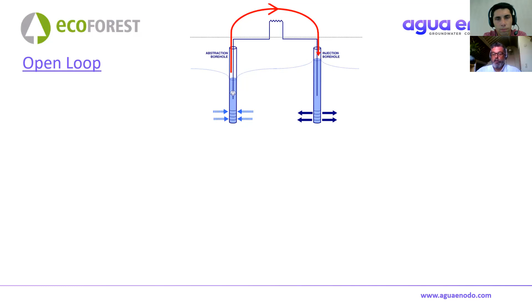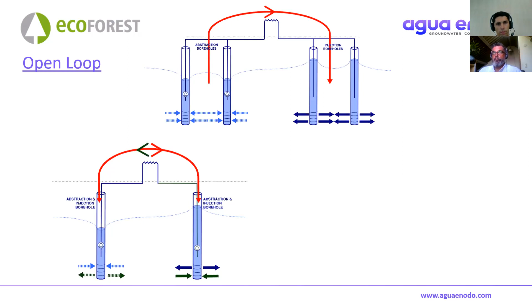Something very popular in the Netherlands, and increasingly elsewhere, is a reversible system, where instead of a dedicated abstraction well and injection borehole, we have a dedicated warm well and a cold well. These are for sites with a fairly balanced heating and cooling load at the surface. We take water out of a cold well when there's a cooling load, warm it up, and dump it into the warm well - and reverse the system when there's a heating load, dumping cold water into the cold well. So both boreholes can abstract and both can accept injected water.